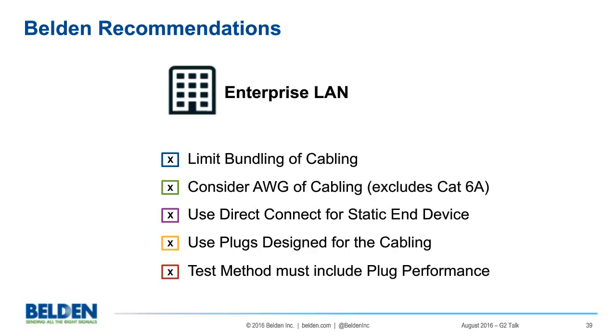Since it's horizontal cabling all the way from the equipment to the end device, you're going to maximize your efficiency because the DC resistance is going to be lowest, and you're also going to minimize your insertion losses because a larger gauge wire has lower insertion loss. Make sure you use plugs that are designed for the cabling. You don't want to put a 5E plug that's specifically designed only for 5E on a Cat 6A horizontal cable. Number one, because it might not fit, and number two, you're going to have a lot of crosstalk in there, and that crosstalk is too great a range in 5E for it to be considered for 6 or 6A.